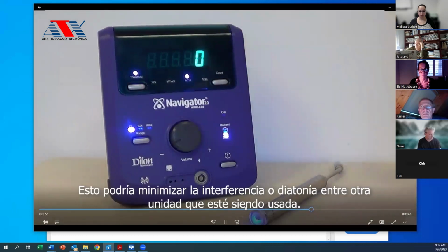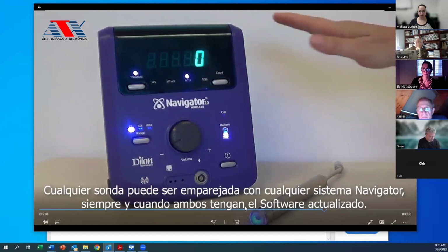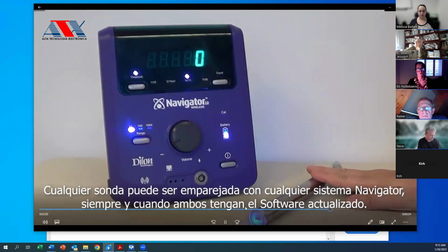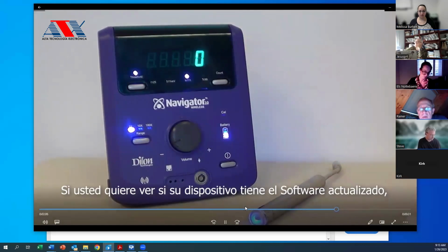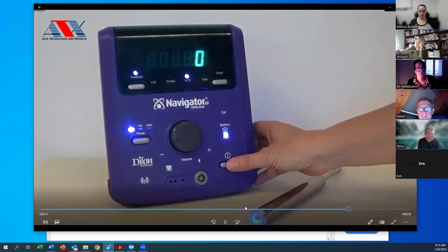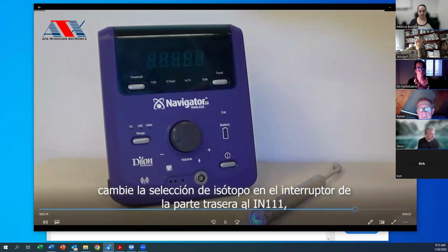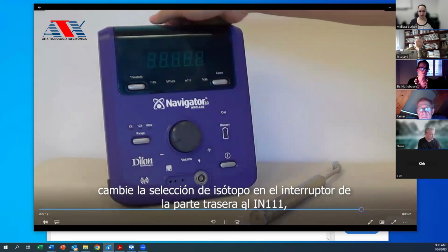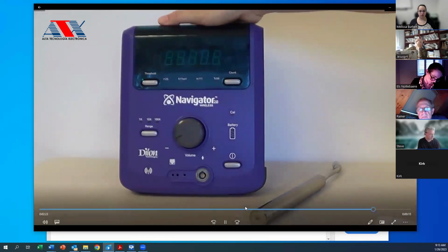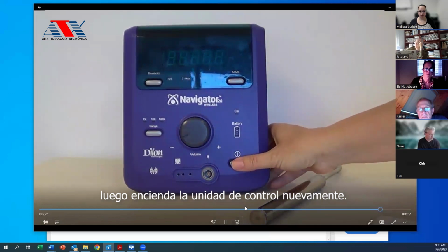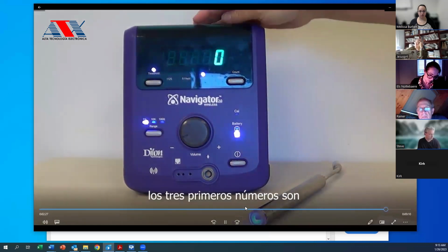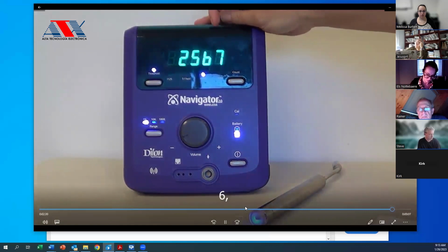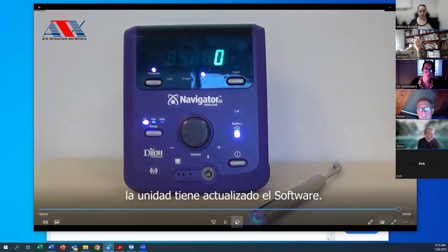This will minimize interference or crosstalk between another unit being used. Any probe can be paired with any Dilon Navigator system as long as they both have the upgraded software. If you want to see if your device has the upgraded software, simply power the unit off. Switch the isotope selection switch on the back to IN111. Then turn the control unit back on. If you see the first three numbers are 2, 5, 6, the unit has the upgraded software.